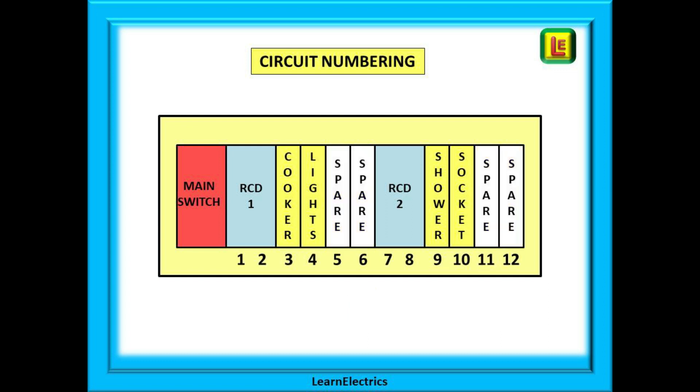The method I use and the way we teach it at LearnElectrics is to number all the ways in strict numerical order. The first way after the main switch is number 1 and a 12 way board will be labelled 1 to 12. Now complete your schedule of test results and write in exactly what is in every way. RCD in ways 1 and 2. Then breakers in 3 and 4. Include the spare ways in 5 and 6. And so on. Way 11 was a spare but we have now added a new circuit in that position. But because we have chosen this better method of numbering it makes no difference to the logic or order of the other circuits. Life just goes on and hopefully this method makes sense.